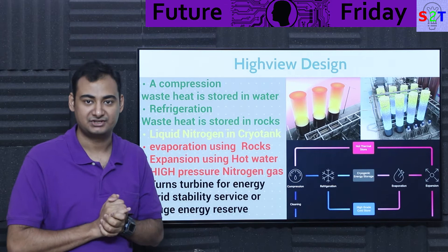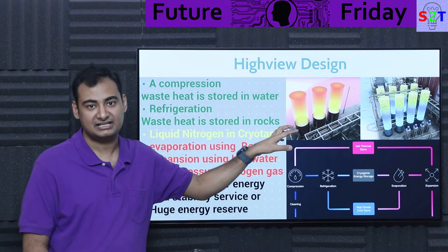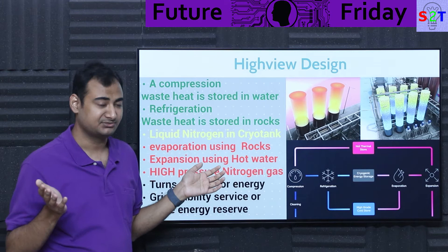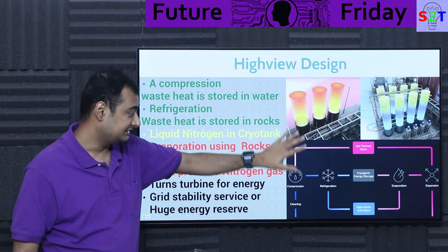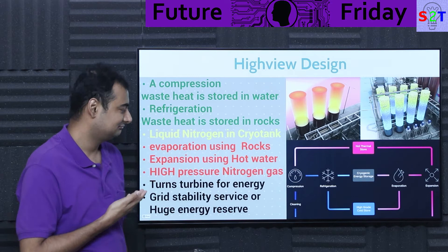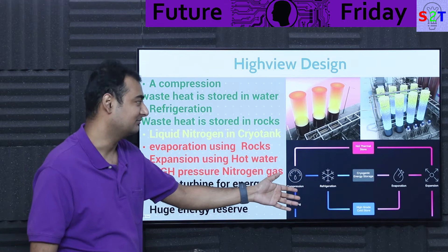Once your liquid nitrogen is in gaseous phase, it's not yet powerful enough to run a turbine. So you utilize the hot thermal store — it passes through a heat exchanger, boosting the pressure from roughly 15 psi up to 300 or 500 psi. Now you have high-pressure nitrogen that can go into a turbine and generate large amounts of energy. These two waste-heat recovery components are the critical innovation here. Anyone could have made a cryogenic energy storage system — nobody did because it was only 25% efficient. After 18 years of work, they figured out how to optimize the waste energy recovery.